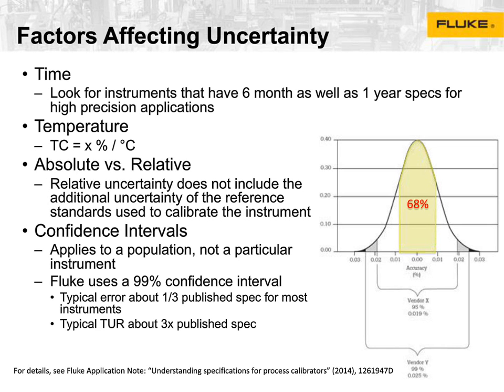The easiest one is probably time. We all know that gauges tend to drift over time, and so most manufacturers, when they publish their spec, it's only valid out for 1 year. Beyond 1 year, if you haven't calibrated your gauge, the manufacturer won't say that it's within a certain error range. And so if you're not getting your gauges calibrated yearly, you don't really know what accuracy you have.